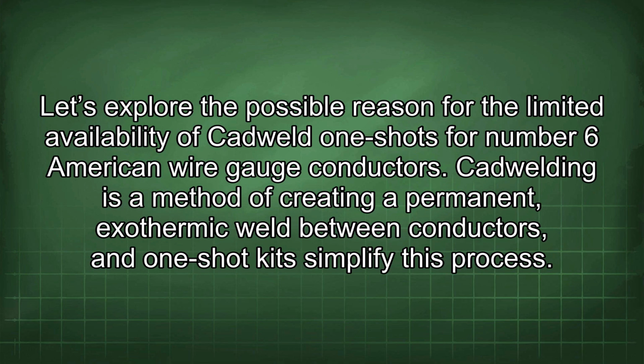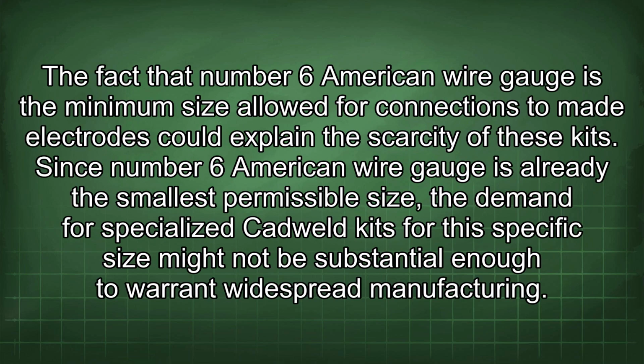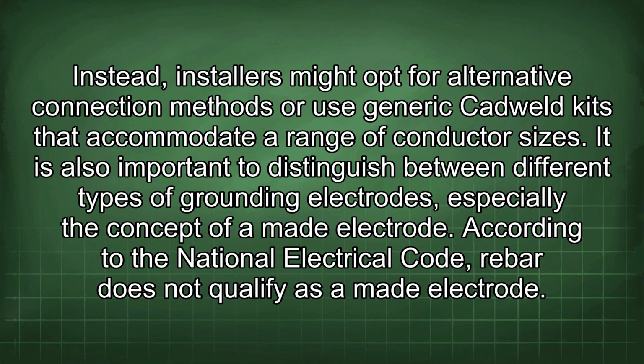Cadwelding is a method of creating a permanent, exothermic weld between conductors, and one-shot kits simplify this process. The fact that number 6 American wire gauge is the minimum size allowed for connections to made electrodes could explain the scarcity of these kits. Since number 6 American wire gauge is already the smallest permissible size, the demand for specialized Cadweld kits for this specific size might not be substantial enough to warrant widespread manufacturing. Instead, installers might opt for alternative connection methods or use generic Cadweld kits that accommodate a range of conductor sizes.